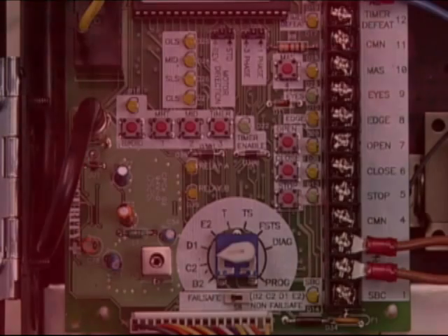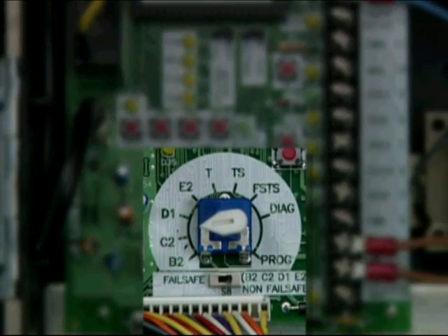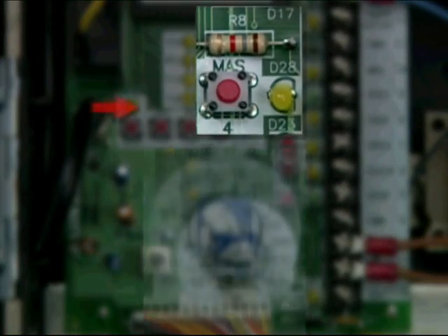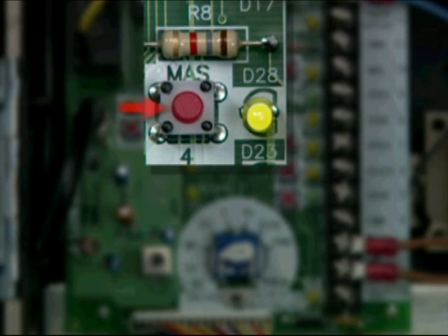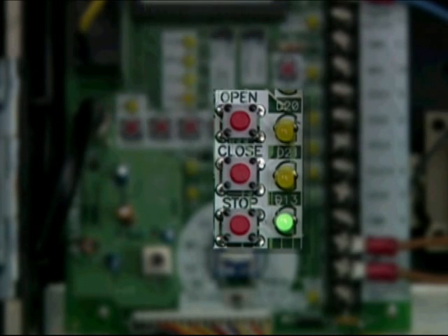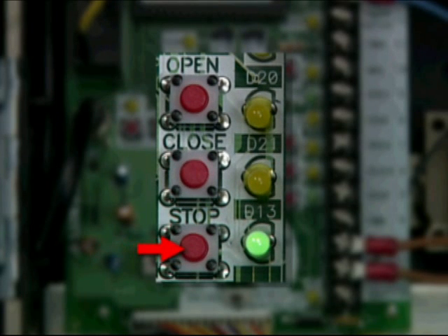Begin with the door in the fully closed position. Turn the selector dial on the logic board to program. Press and release the MAS button on the logic board. Press the stop button on the logic board to zero the MAS counter. Press the open button once for each 5,000 cycle increment desired. Press the close button once to set each 3-month increment desired.